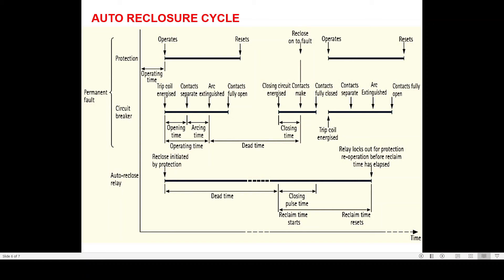Now we will discuss the complete autoreclosure cycle. Once the protection relay sees a fault, it will operate, but this generally takes some time — about 20 to 30 milliseconds. Although zone 1 timing is 0 milliseconds, that doesn't mean zone 1 will operate at exactly 0 milliseconds. It will take some time depending upon relay processor speed, sampling of the numerical relays, availability of current and voltage magnitude, and the algorithm of your distance protection relays.